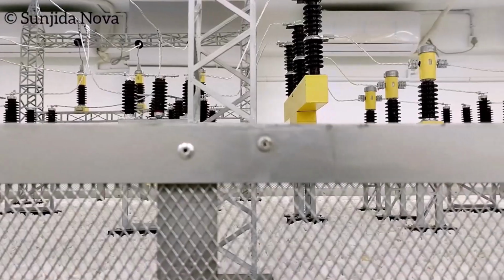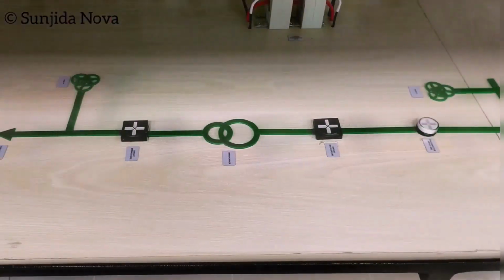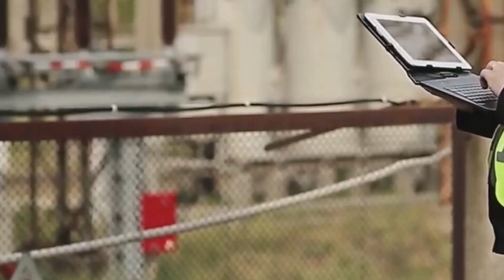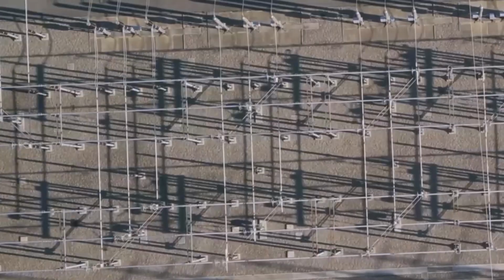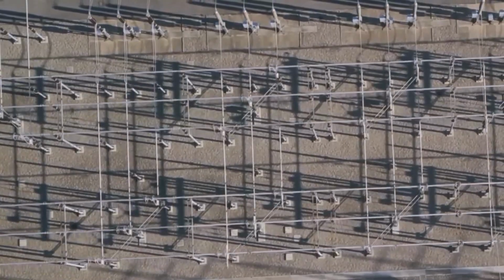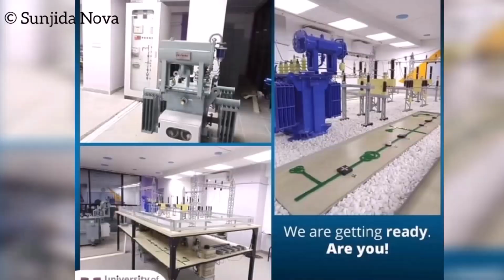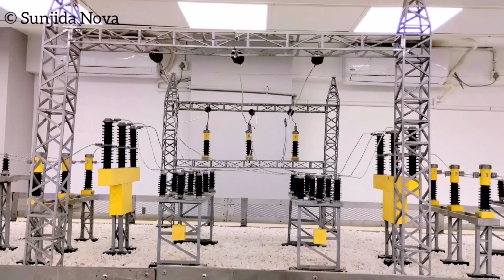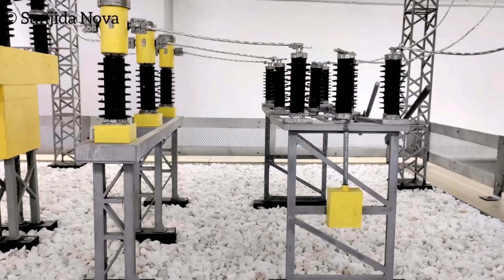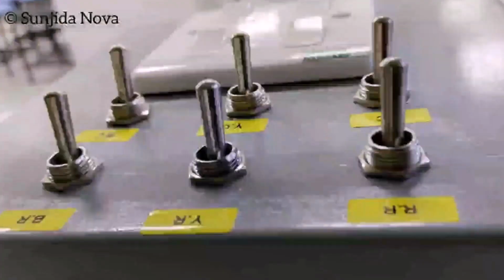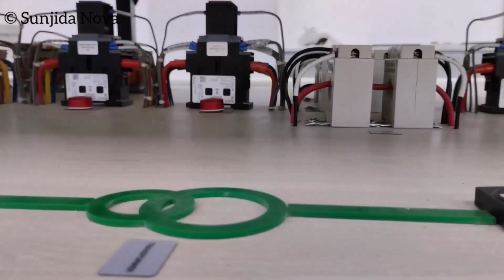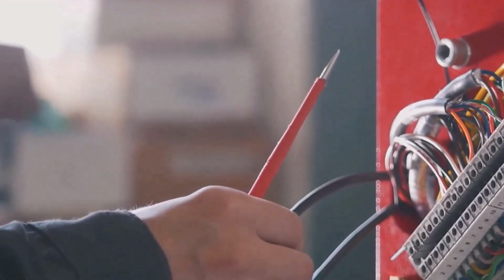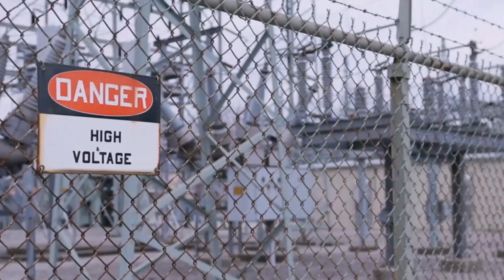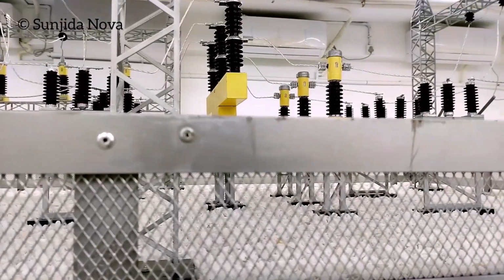One of the most important safety steps is called de-energizing. This means the equipment that is going to be tested is completely disconnected from the power grid. You would never try to fix a toaster while it's still plugged in, and the same idea applies here, but on a massive scale. Technicians use switches to isolate the apparatus, and then they apply safety grounds. These are special cables that connect the equipment to the earth, ensuring that no stray or unexpected electricity can flow through it and cause a shock. This creates a safe work zone where the team can connect their testing instruments without risk.